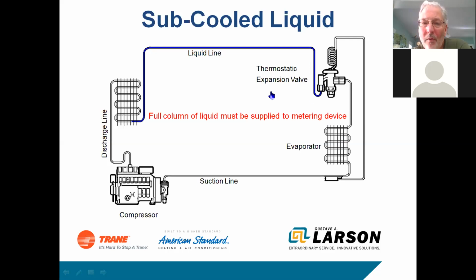Okay, so with 10 degrees subcool, we feed the valve liquid. The valve's happy. It feeds the evaporator properly. The expansion valve's job is to try to maintain somewhere between 8 to 12 degrees of superheat. Some of the more high efficiency systems, you might see 18 to 20 degrees of superheat, okay? So just make sure that we're feeding that valve properly, and that's what the subcool is telling us. As long as the valve's fed properly and we're at 8 to 20 degrees of superheat, the valve's probably working fine, and it's feeding the compressor the way it needs to. Everything should work at that point.